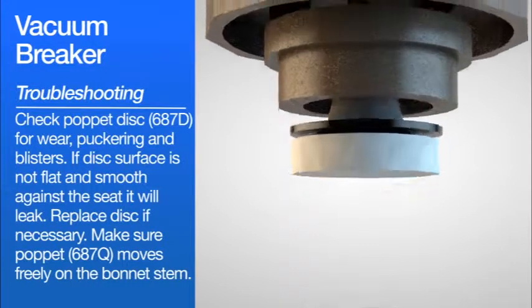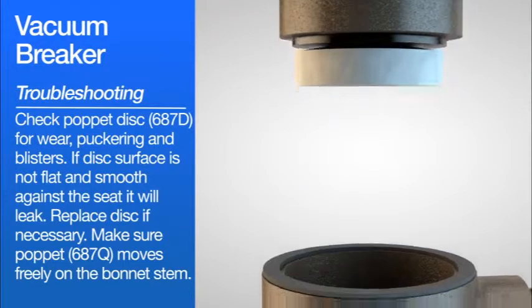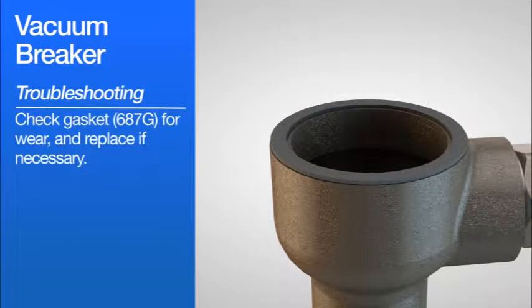Make sure the poppet 687Q moves freely on the bonnet stem. Check gasket 687G for wear and replace if necessary.